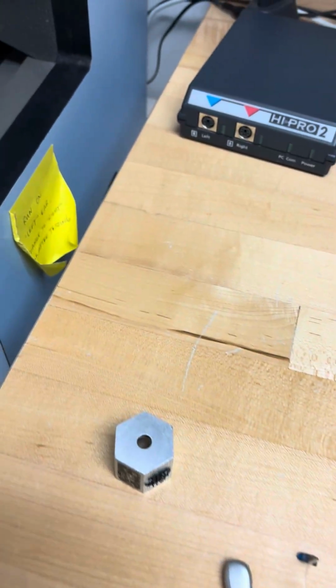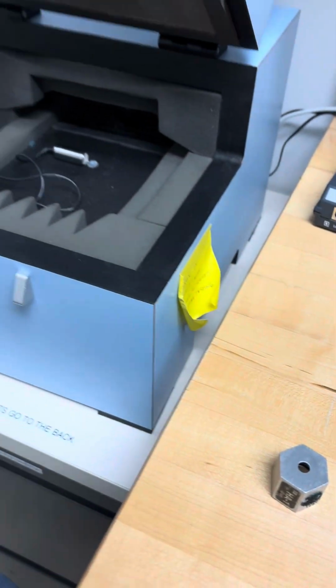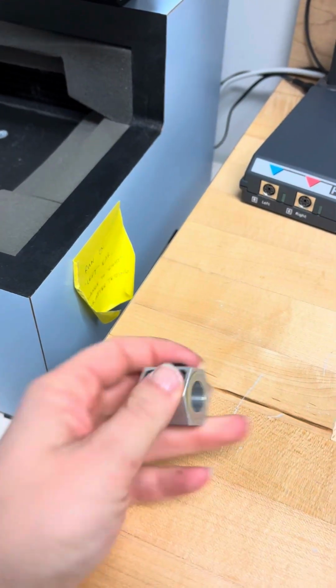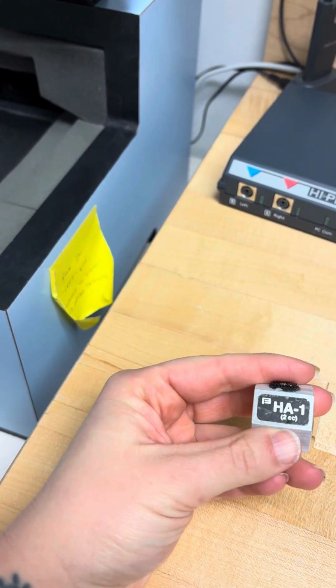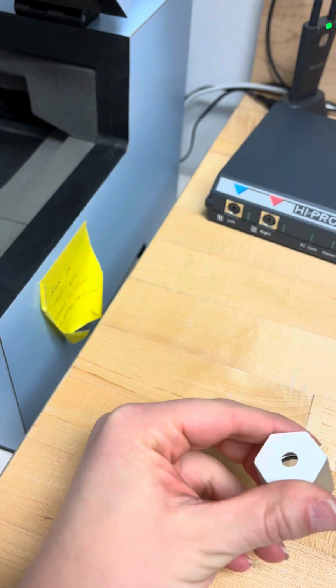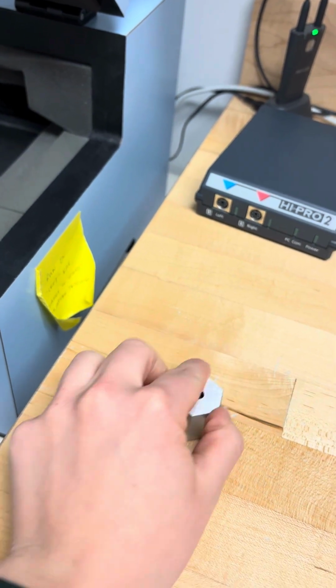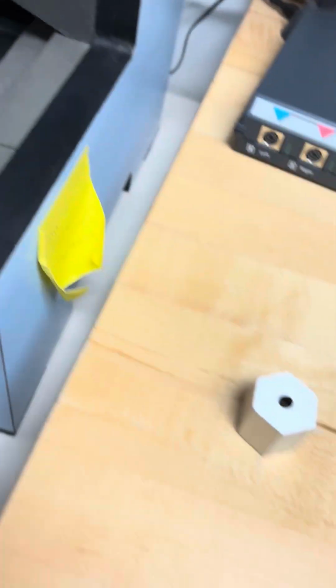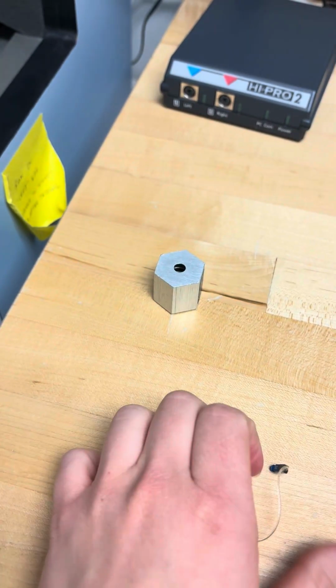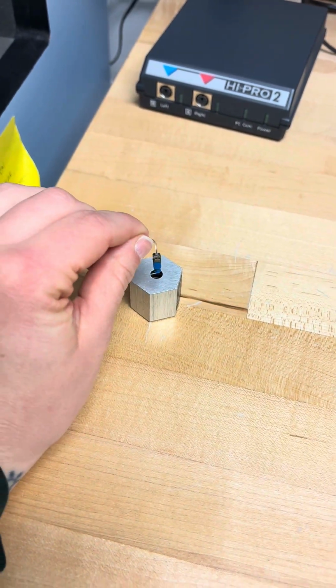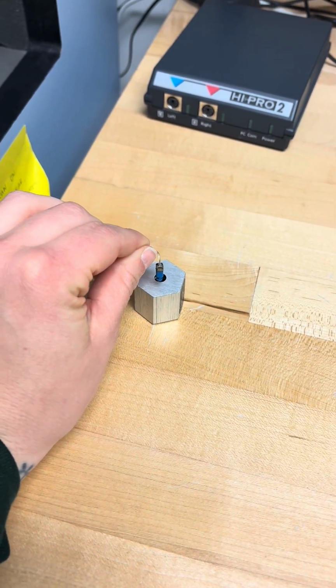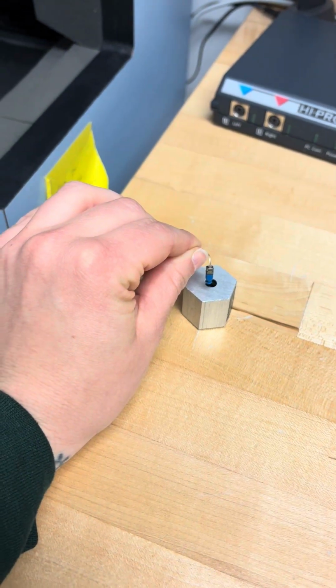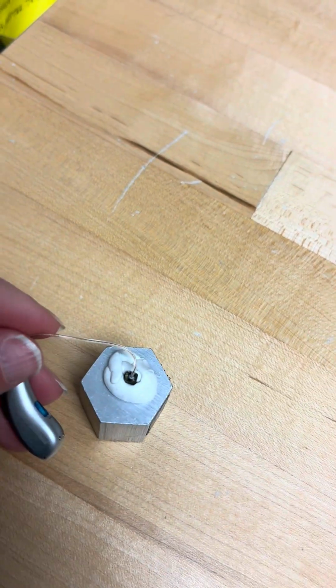And then we want to set the hearing aid up in the Fonix box. So we are going to get the correct coupler. So the 2cc, and this is for a RIC. We want to grab our putty and put our hearing aid flush with the opening and wrap putty around it. Should end up looking like that. And then we are setting our hearing aid to full on gain.